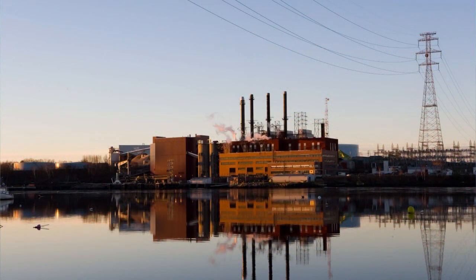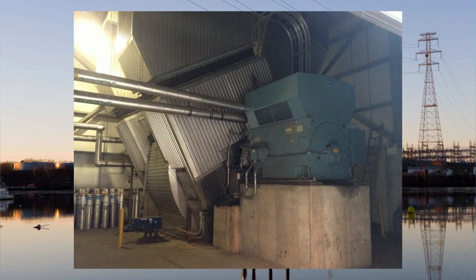This 50MW Schiller Biomass Power Station facility, the largest in the States, had a serious fan noise problem. This was solved by deciding to use Quiet Fan technology. Installation took only 12 hours on this massive 3m wide fan. It reduced the tone by some 10dB, which eliminated the problem and also reduced the power consumption of the fan.